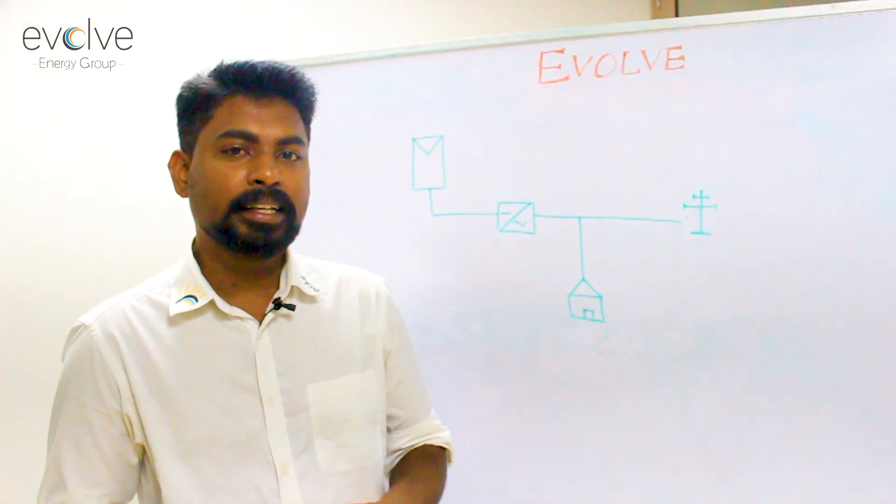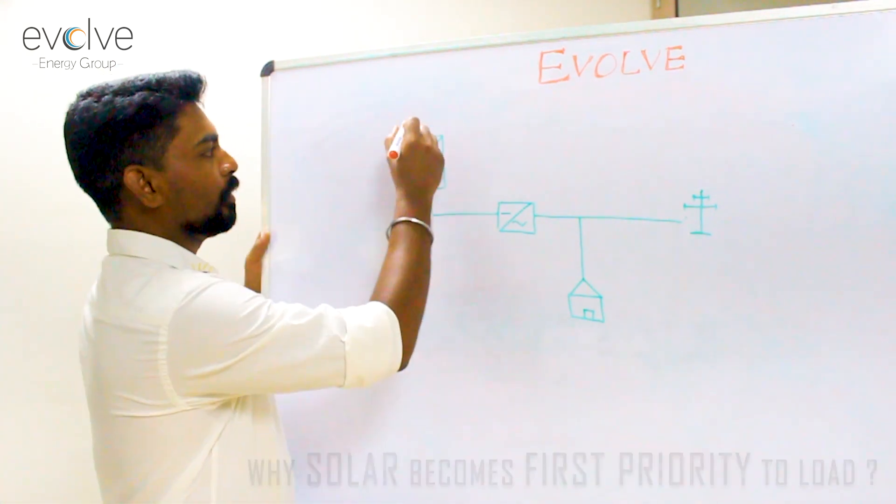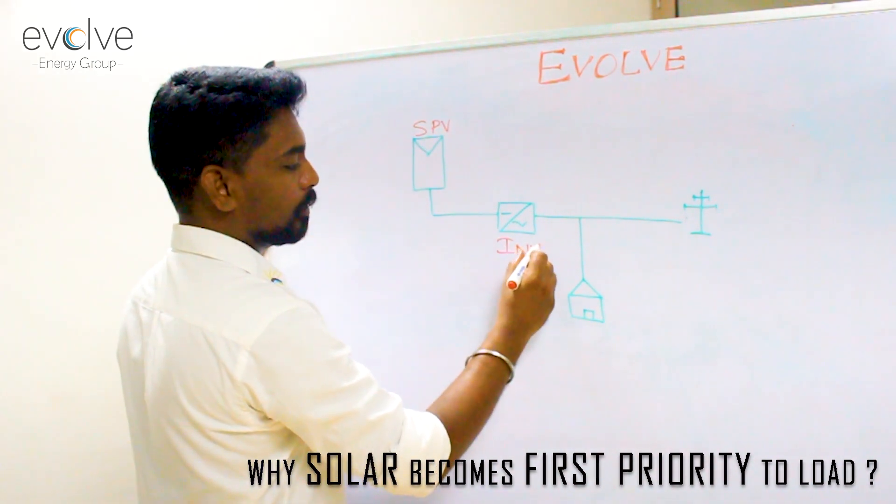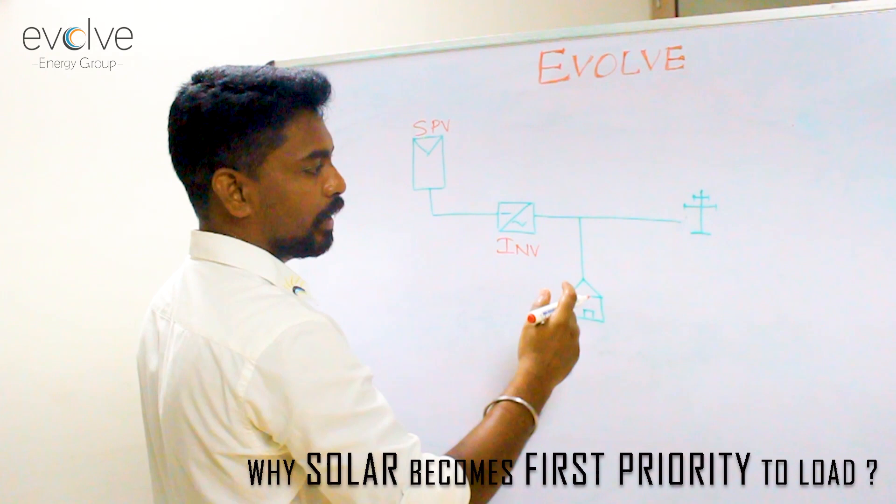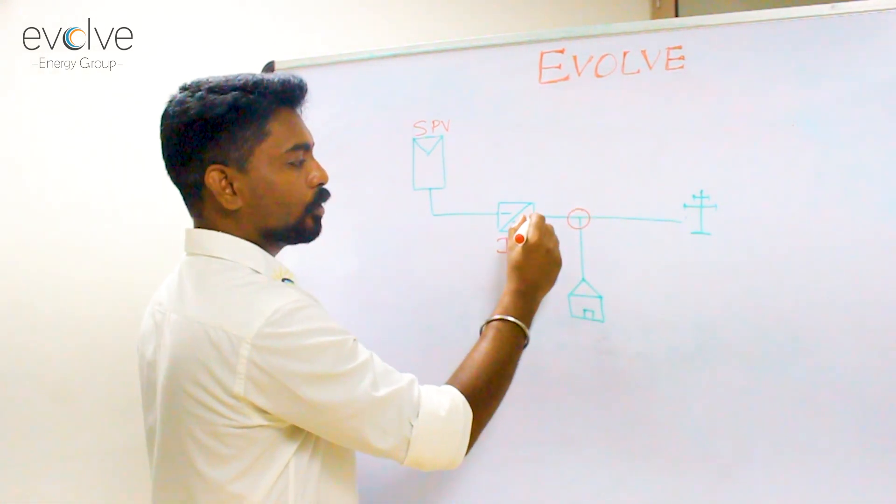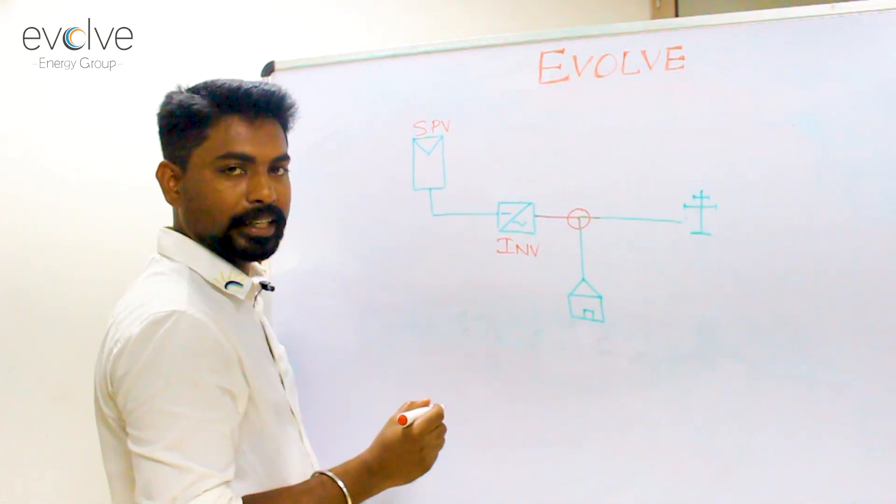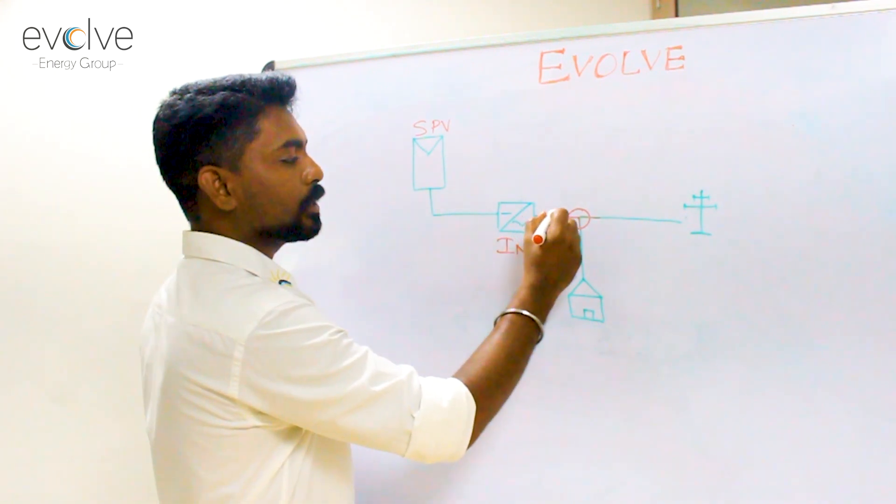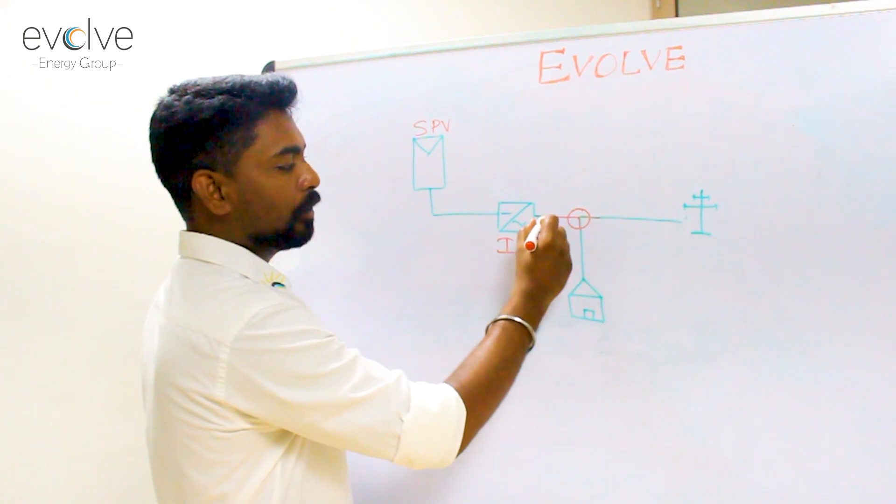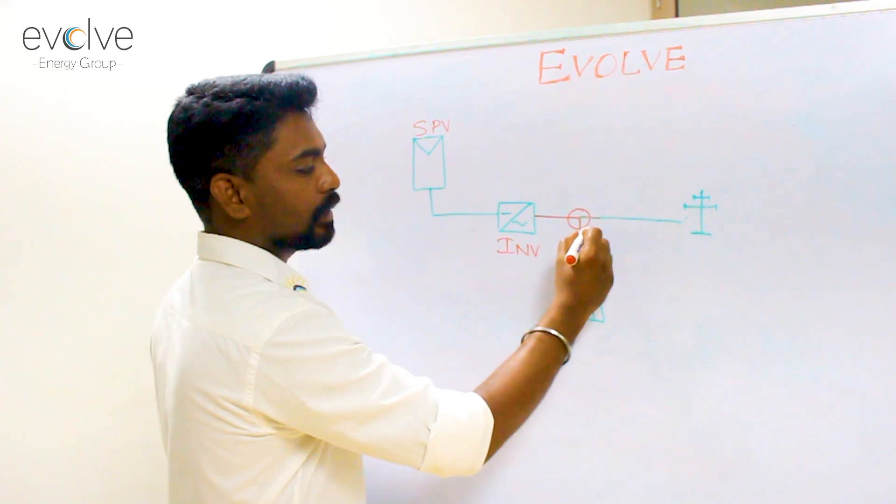With those two examples we'll just move on to the real-life scenario with the solar panel connected to your inverter powering up your load and also connected to the grid. And this is the point where the solar power meets the grid power and this is the point where your solar inverter produces a voltage a little bit higher than the grid which makes it push its power into the load and the excess into the grid.